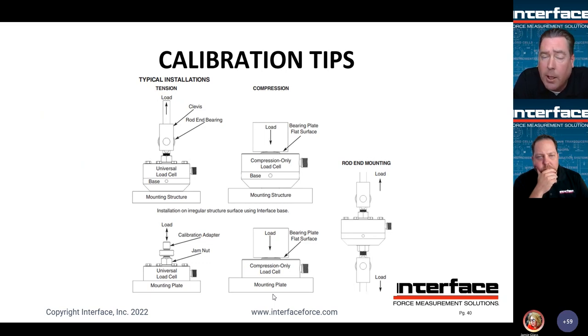The one on the right, not quite as applicable. It could be if you were doing a tension calibration. So yeah, I suppose it could be. So this is an example with rod end bearings that are jammed into both sides. Again, you're jamming above capacity on each of those ends, and they're being loaded in tension through those rod end bearings through a clevis into the load string. Obviously, this setup would be great for tension, less than ideal for compression, so would not recommend doing that.